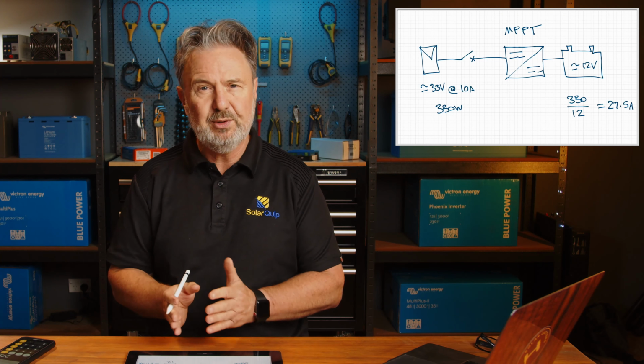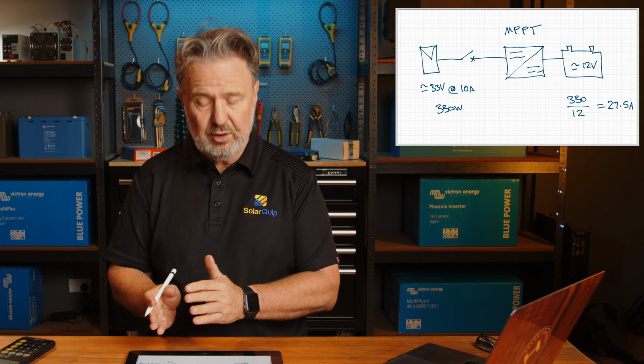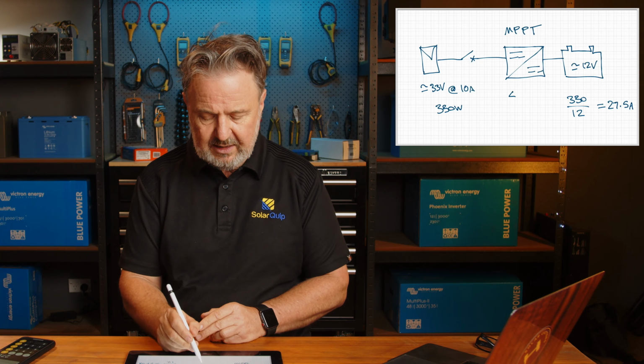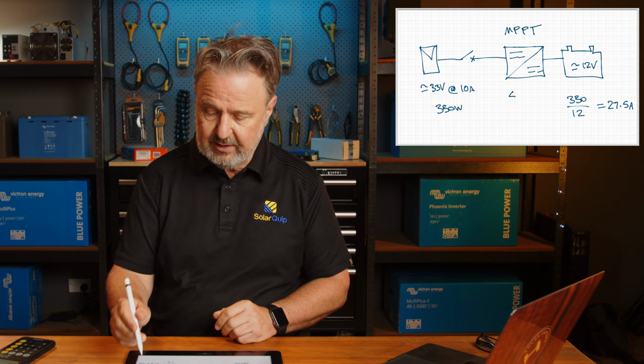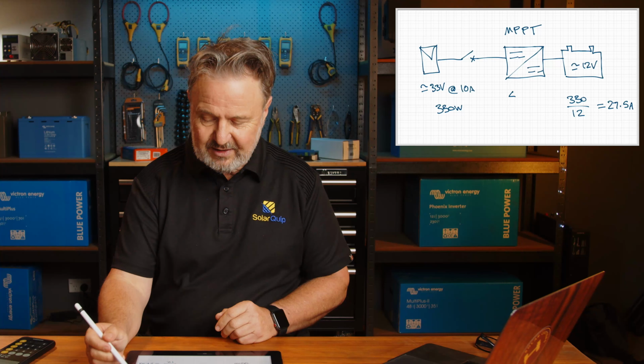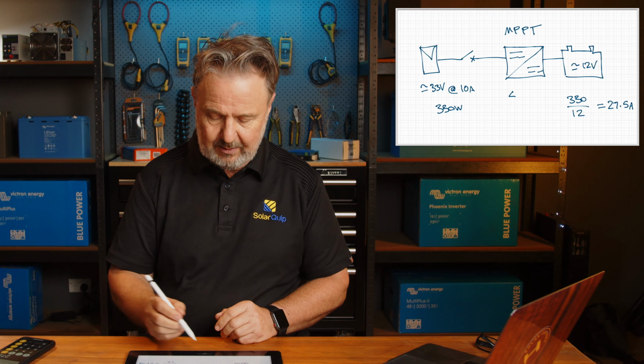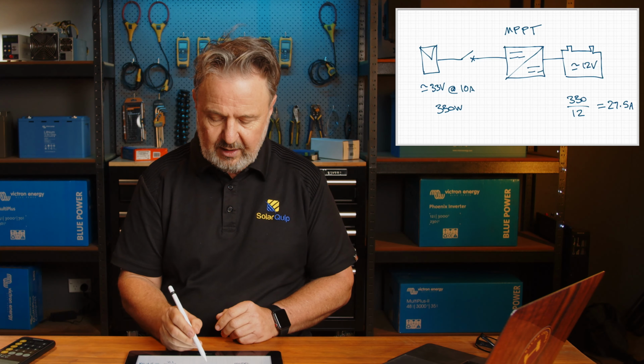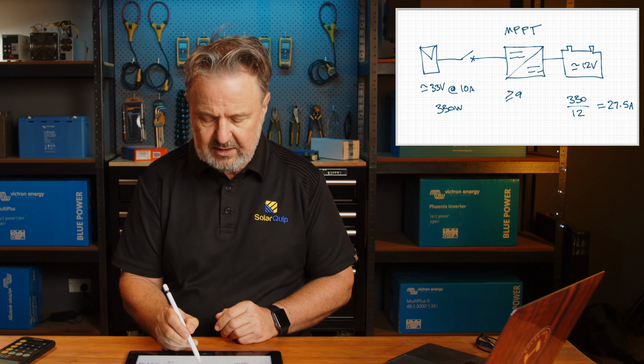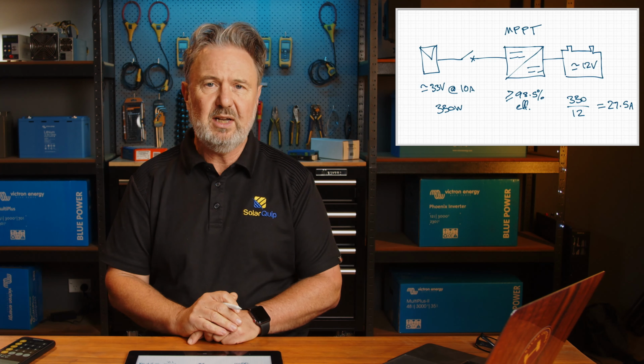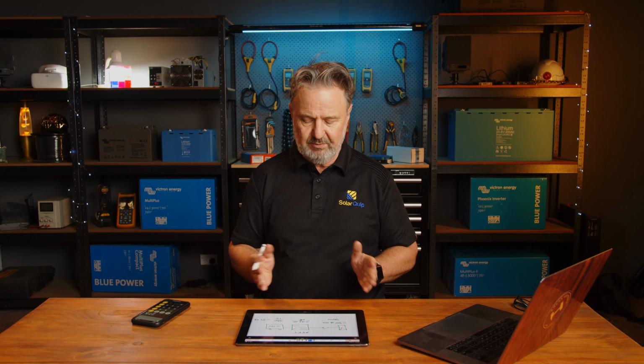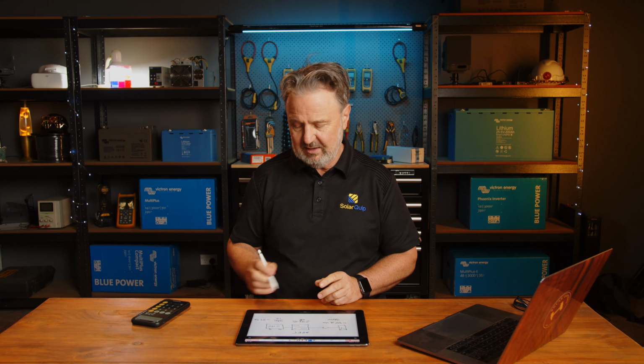Of course there is a small efficiency loss in that conversion process. Typically it's greater than - let me just go back a step there - it's greater than something like 98.5% efficient. So efficiency is pretty high on charge controllers, some of them are over 99% efficient. So I'm ignoring that efficiency factor when I'm talking about the amps going into the battery.